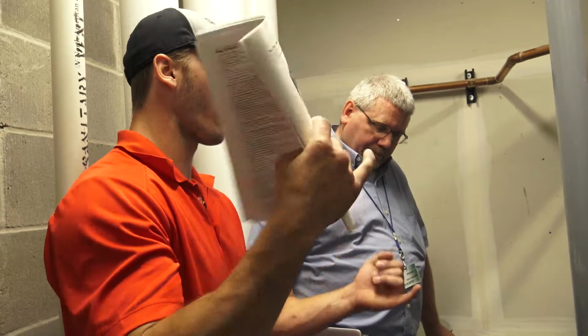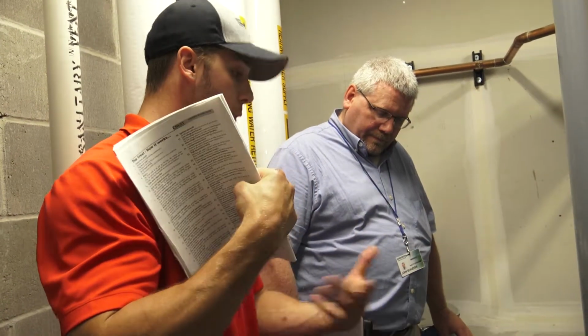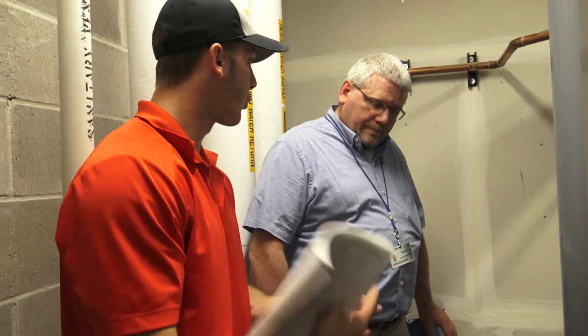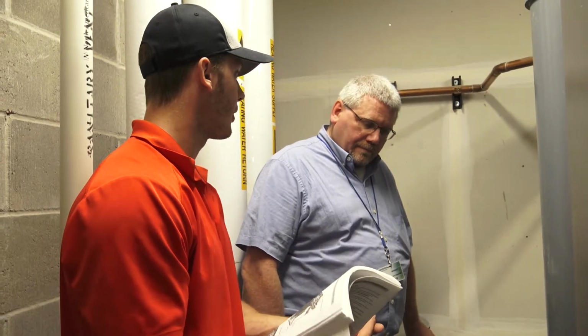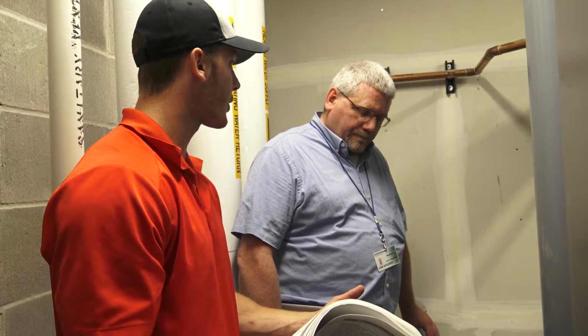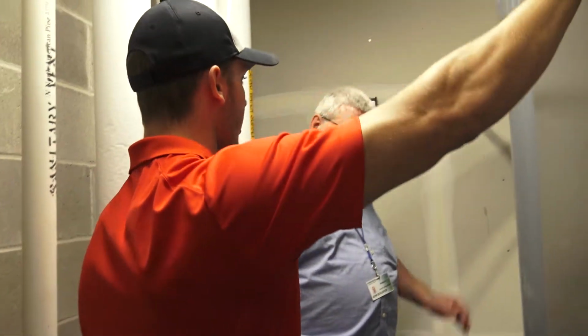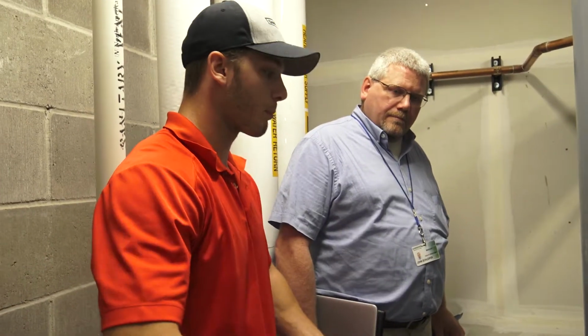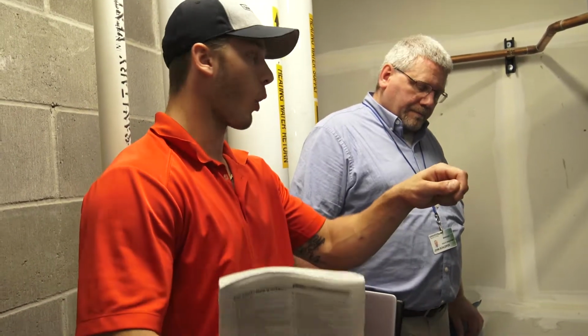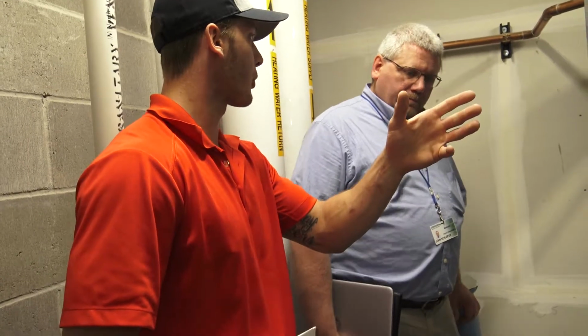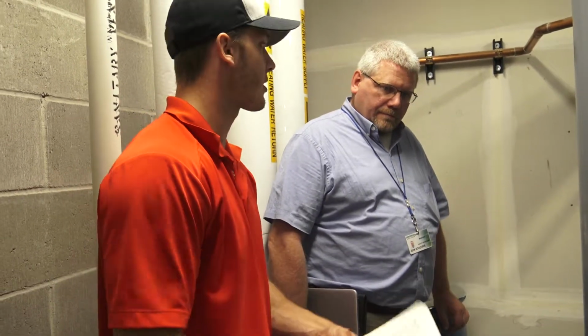So like yearly inspection. Personally, if it was me, and what they recommend: new igniters, new flame sensors, and clean the burner once a year. Inspect the heat exchanger. On top, it's pretty self-explanatory. Remove the bolts, take off the top plate, pull the burner straight out, take an air hose, and blow it out. It is a metal mesh burner, so you can spray it down with water. Doesn't matter how you clean it. I wouldn't be gunking soap and stuff on there, but water and air are definitely acceptable.